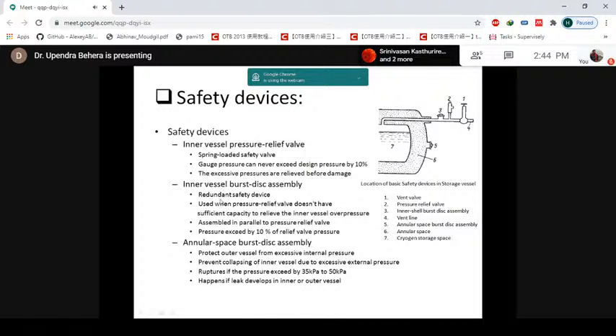And if, for some chance, the safety valve is not opening, or is unable to vent the quantity of gas inside the vessel for some reason, if the pressure is very high and more volume flow needs to escape from the container and it's not able to handle it, that time also this rupture disc takes care. And this is again set 10% more than the set value of the relief valve. That means 20% of the design pressure. So when the pressure is more than 20% of the design pressure, and the relief valve is not able to handle it, this bursting disc will open up and the container will be depressurized. But the relief valve is a two-way process, meaning once the pressure is relieved, it can automatically close and the container can be utilized, and later you can remove the liquid.